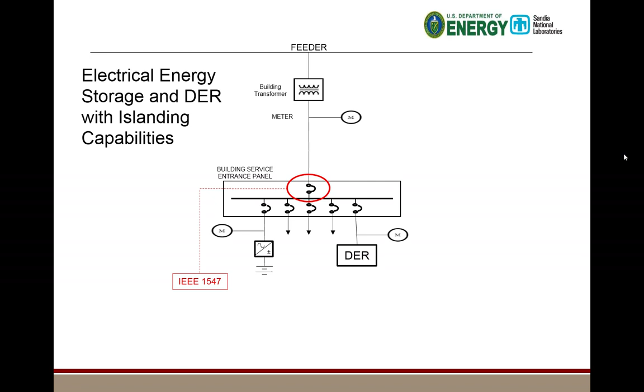One thing to note is that in the red you have the IEEE 1547. Most inverters are required to shut off in the event of a power outage on the grid. If you want to do islanding, this is a problem. I've been doing some research on this. It looks like the inverters can be reconfigured to allow ride-through, but your utility may still require the 1547 compliance. In that case, you would need to provide a relay or some sort of tripping mechanism up in your main feeder breaker that will isolate you from the grid and allow your battery to operate with your distributed energy resources.